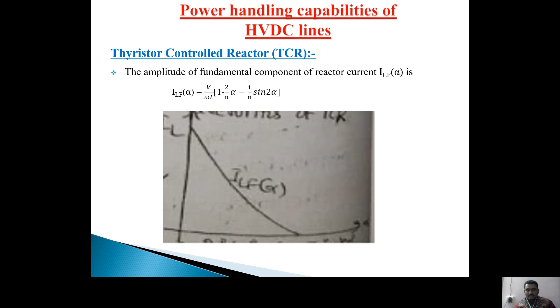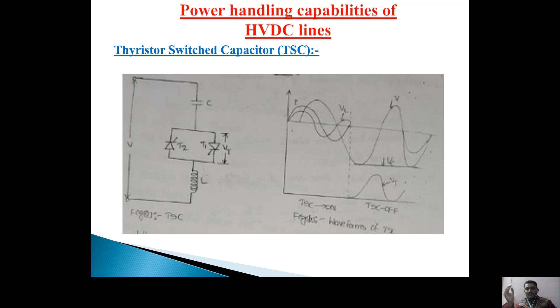So next, coming to the thyristor switched capacitor. On the left side we have the thyristor switched capacitor diagram. Here I am connecting the capacitor to the bus bar, and it consists of the thyristor valve or switch, and it also consists of a reactor. On the right side we have the waveforms for this operation. Here we are taking the supply voltage waveforms when the TSC is on and when the TSC is off. When the TSC is on, the left side of the waveforms appear, and when the TSC is off, the right side of the waveforms will appear.